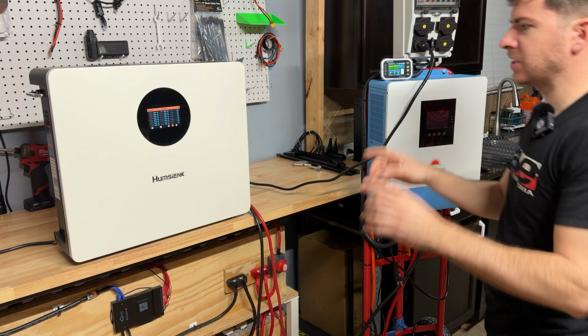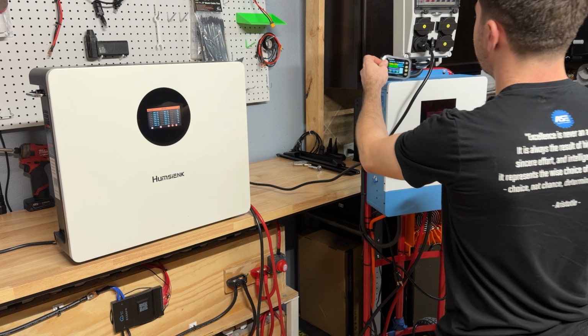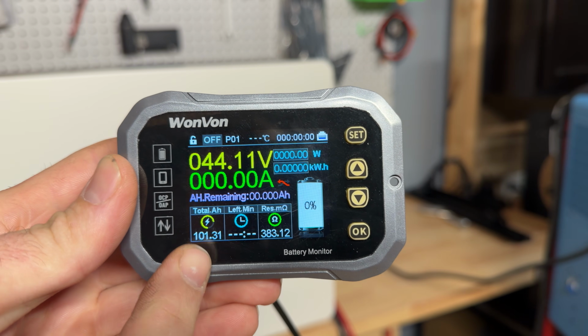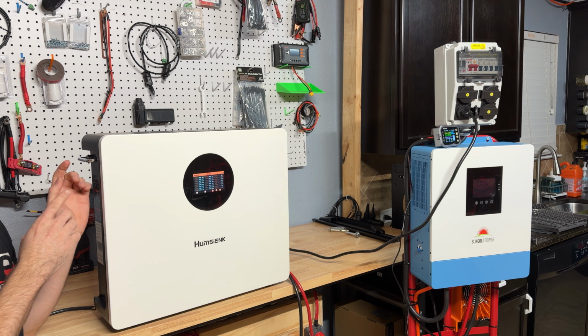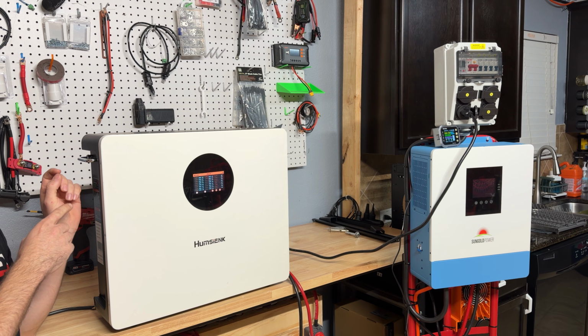We just finished the capacity test on our Humsienk wall battery, and it got a grand total of 101.3 amp hours. So it passed the capacity test, pulled a little bit over 100. That's good to see. We were able to get the full capacity as advertised out of the battery.